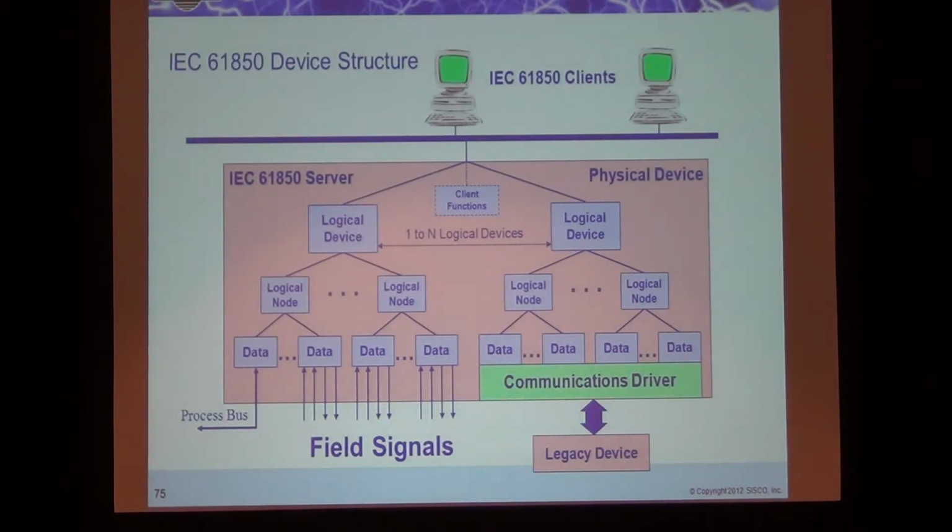Models. This is just a high-level drawing of a 61850 object model. The physical device is represented by a server function. The servers are essentially the devices: protection relays, RTUs, breaker controllers, things of this nature. That's what the physical devices are.